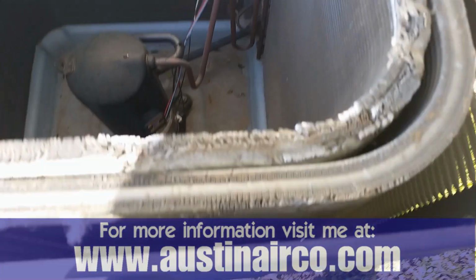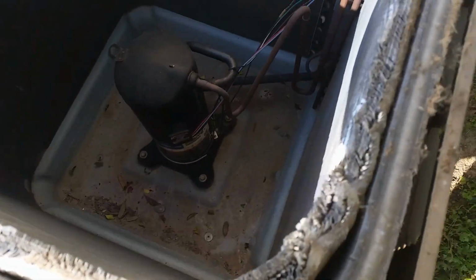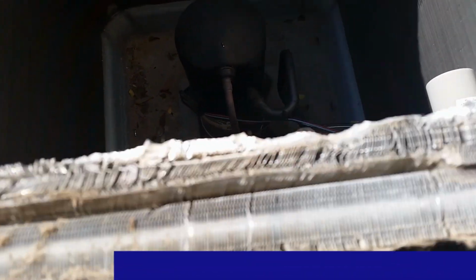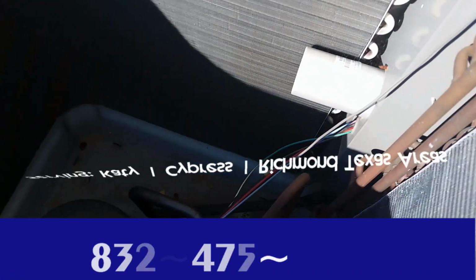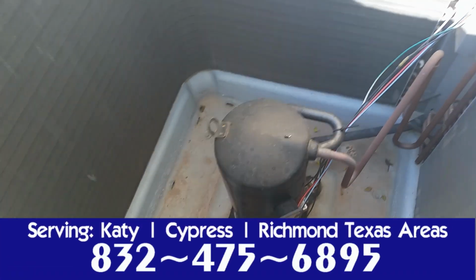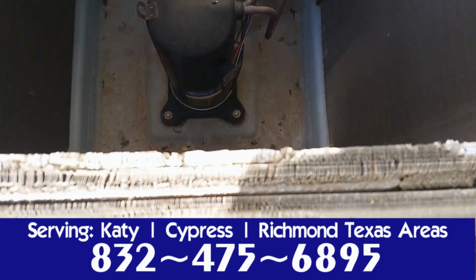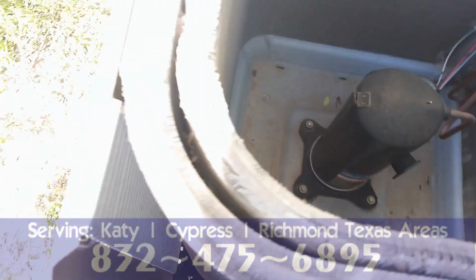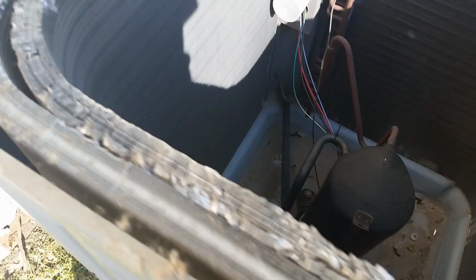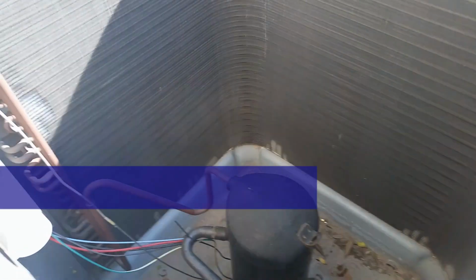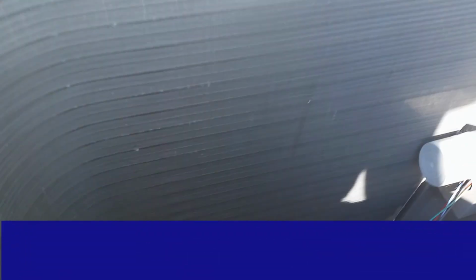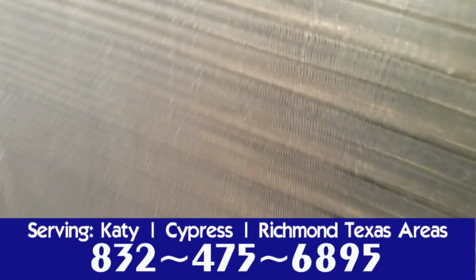This unit was built around a time when efficiencies were going up, but manufacturers were still allowed to use R22. So they double stacked the coil, making the condenser coil double thickness. The total charge on this unit was probably around 17 to 18 pounds of refrigerant. Prior to this time span, refrigerant charges were quite a bit less, anywhere from 6 to 8, maybe 10 pounds. That's another factor in deciding whether it's worth keeping the equipment.